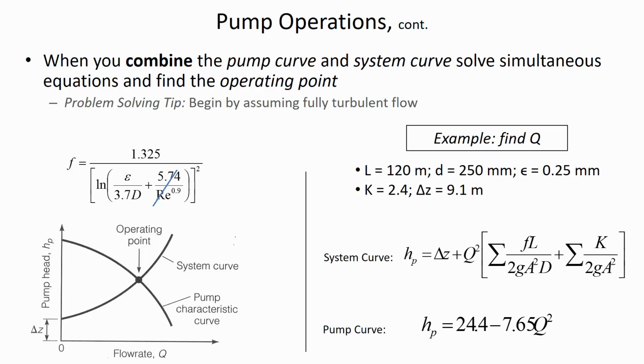So you can put all of those parameters into the system curve and set it equal to the pump curve. This is that same pump curve that came from the earlier diagram. So what we want to do is find the operating point. In other words, solve for Q. The first thing you're going to need to do, after calculating the area and so on, is use the fully turbulent flow assumption to find a starting point for your F.